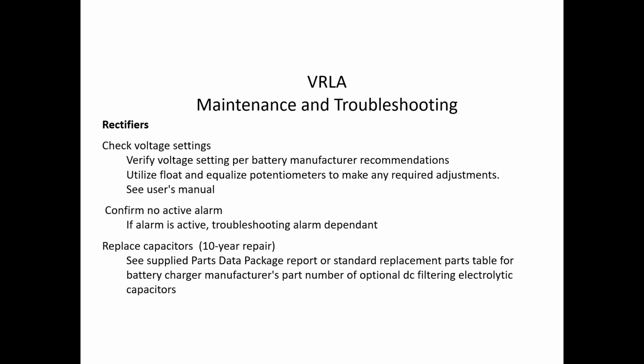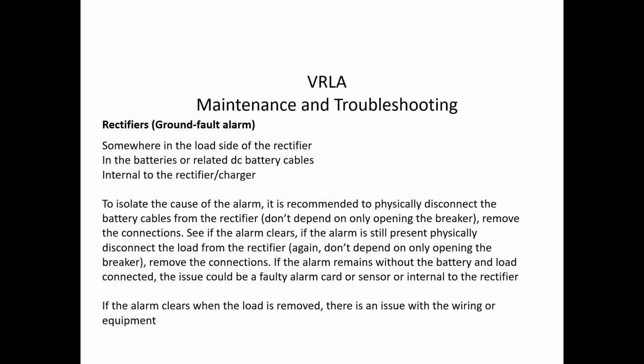We saw a couple of those negative ground alarms on the ungrounded systems. I touched base on that because I know that we have had that issue. The capacitor replacement is usually on a 10-year interval is what they recommend. Rectifier ground fault alarm, because I know that we've touched base on this situation in the past, I wanted to make sure that I incorporated it into this presentation.